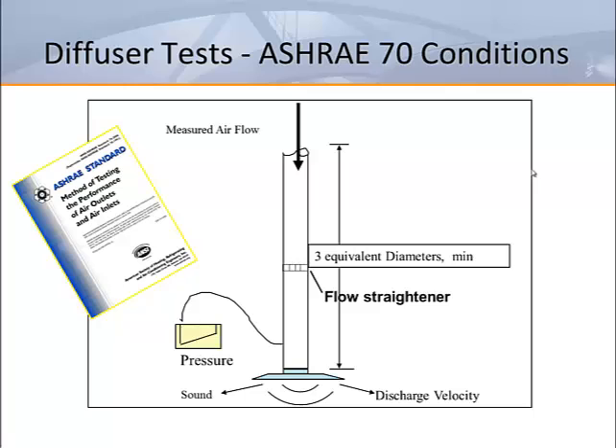Another factor affecting sound from a ceiling diffuser is the inlet conditions of the supply air connection. ASHRAE Standard 70 prescribes the method of test used by manufacturers for air inlets and air outlets. For sound testing, the standard requires a minimum of 3 diameter equivalents of straight duct with a flow straightener to ensure that non-turbulent airstream fills the duct at the entrance of the test device. Since these ideal conditions vary for most field applications, we will look at the impact of common field installations on the room NC.